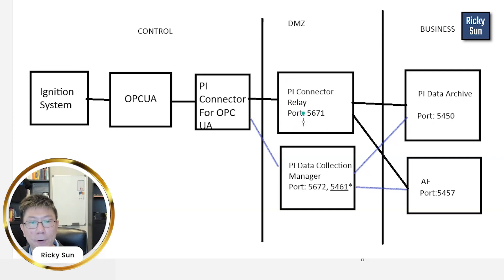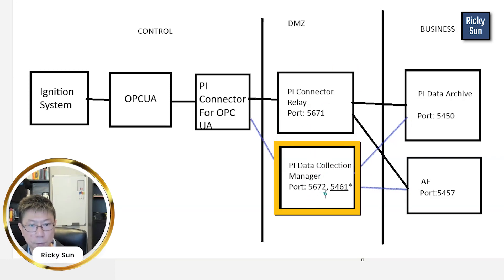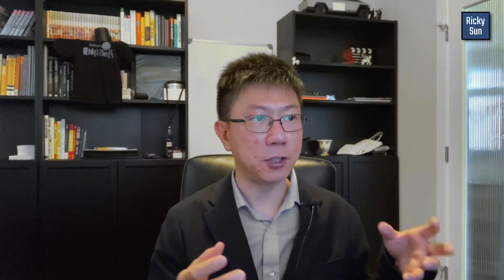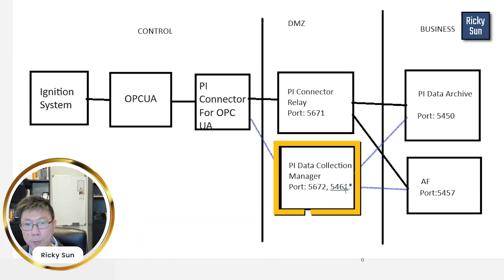There are three ports you need to open. I installed both of these software on the same machine. I need to tell IT that port 5671 needs to be open because it is listening, and then 5672 for PI data collection manager. Also this custom port, 5461 — it can be something else for you when you install PI data collection manager, so this is customizable. You need to tell IT you need this port to be open.